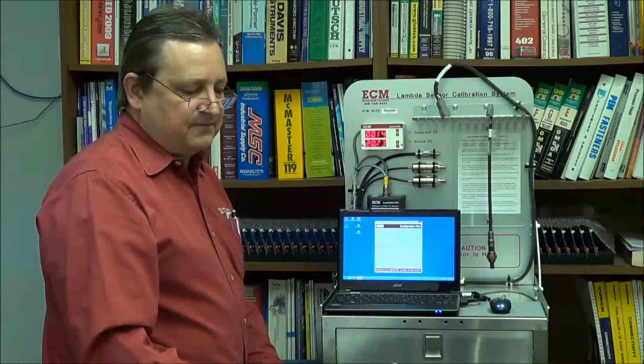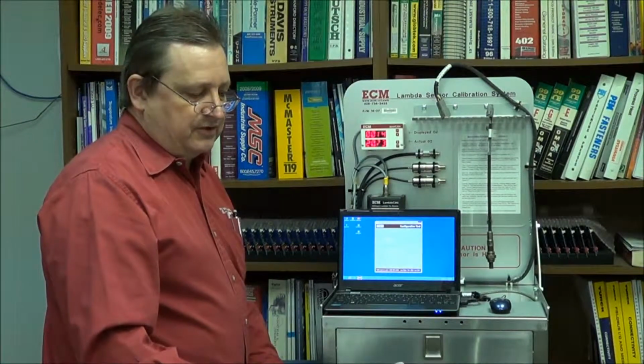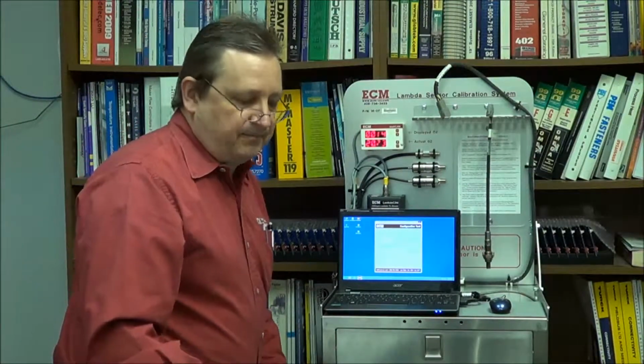The Lambda sensor is a device that measures a gas composition and outputs this composition via an output current. Thus the calibration of the sensor requires an accurate knowledge of the composition of the span gas and the ability to accurately measure the sensor's output current. The span gas we're using, air, is 20.945% O2 minus the amount displaced by humidity. And that's no matter where you are in the world. So the calibration depends on how accurately you can measure the humidity displacing the air.